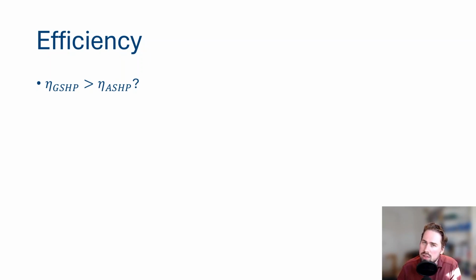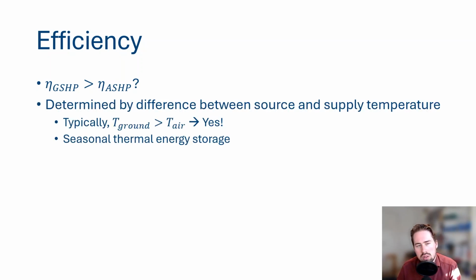Now, is that so? Well, the efficiency of a heat pump is actually determined by the temperature difference between the source of the heat and the supply temperature of the heat. So, the colder the temperature is you get your heat from, the lower your efficiency will be. So, since typically the ground temperatures during a heating season, during winter, is higher than the air temperature, yes, your ground source heat pump is more efficient than your air source heat pump. And this higher ground temperature is also because of something which is called seasonal thermal energy storage, namely that when you work with a geothermal system, you're not only using the ground as a source, you're also storing heat into the ground. So in summer when you're cooling, you store this heat into the ground, whereby you raise the ground temperatures, and this higher ground temperature gives you a higher efficiency for your heat pump. And this is why typically the efficiency of a ground source heat pump is higher.